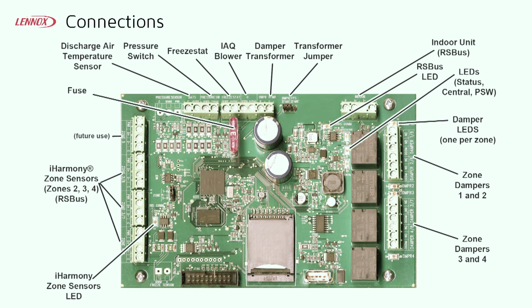Here on the left-hand side is where your zone sensors are going to get installed. Again, they're 12 volts DC. You'll have a power, a common, and then a plus and a minus. That's basically a comm light for your zone sensors. Of course, you'll have your fuse, and then your terminals up here where we'll connect the discharge air sensor, your heat pump pressure switch, your freeze stat. There's a bridge that we'll install there from the factory. A blower sense terminal, which isn't really used in most situations. And then your damper transformer and the transformer jumper. We'll talk a little bit about that coming up.